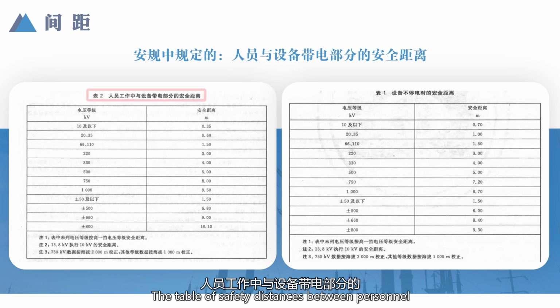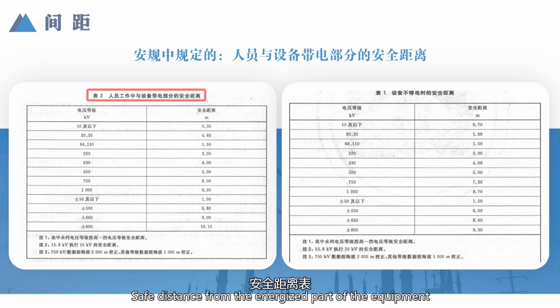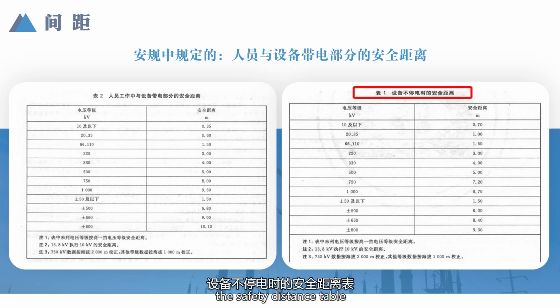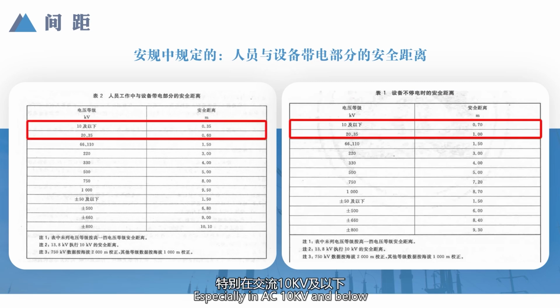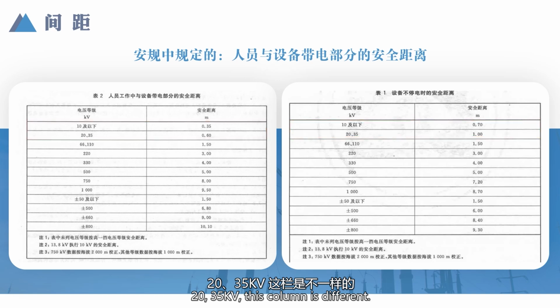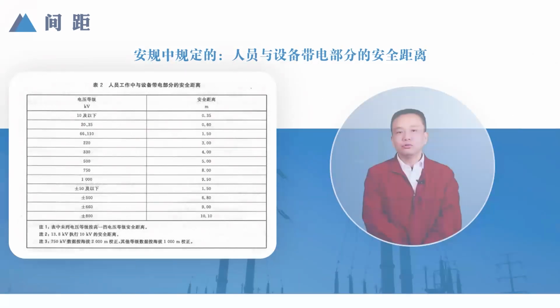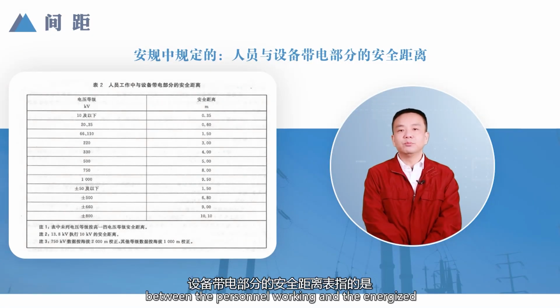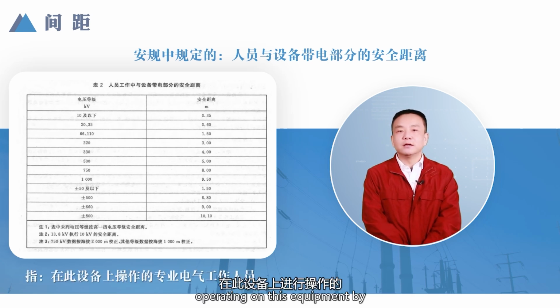One is the table of safety distances between personnel and energized parts of equipment. The other is the safety distance table when the equipment is not energized, especially in AC 10 kilovolts and below, 20-35 kilovolts. This column is different. Is there any difference between these 2 tables? The table of safety distance between the personnel working and the energized part of the equipment refers to operating on this equipment by professional electrical staff.